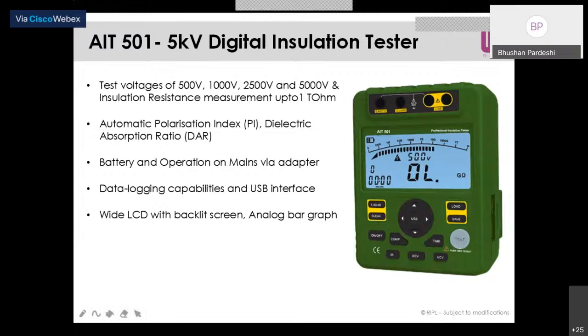Whenever your battery gets discharged, you can connect the mains to the instrument, and parallelly your battery will get charged, and you can also operate on your mains. So this is the benefit of giving the battery as well as mains in this instrument. Now, when I say diagnostic test, that is polarization index and dielectric absorption ratio. These tests are basically provided to check the insulation of any device.